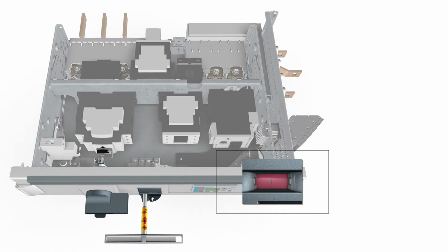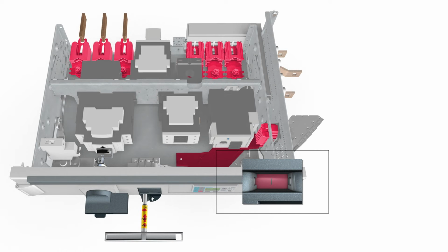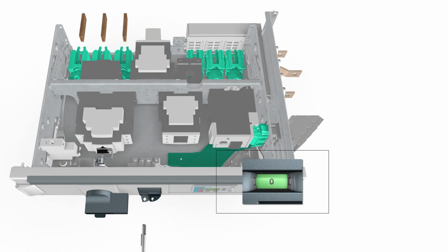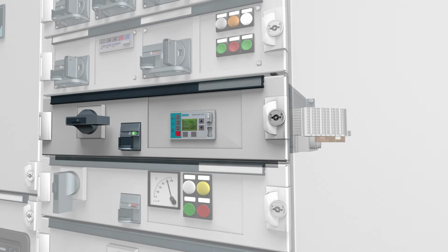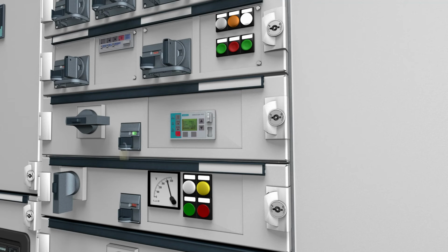In the connected position, the main and control circuit are closed. In the isolated position, the main and control circuit are disconnected. In the test position, the main circuit is disconnected and the control circuit closed. The withdrawable unit can remain in the compartment with the door closed and can be additionally locked in this position. The degree of protection is maintained.